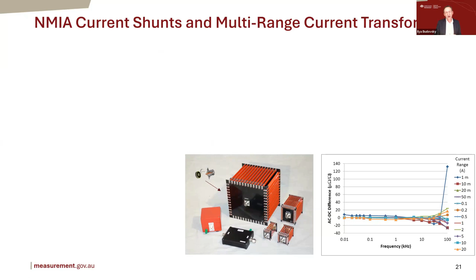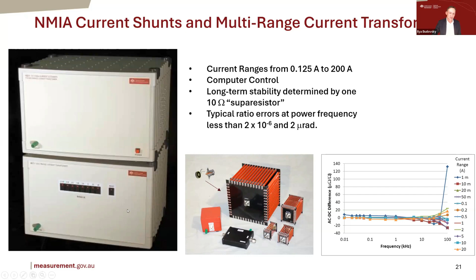For automation, we've developed a multi-range current transformer where the computer can switch primary windings and no shunts need to be changed during the measurements. So we can go from fractions of an amp to hundreds of amps, or 200 amps, using a computer.